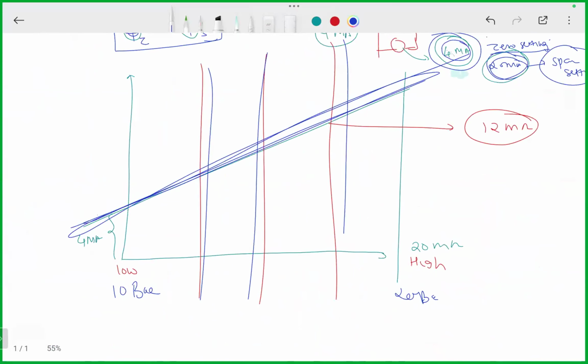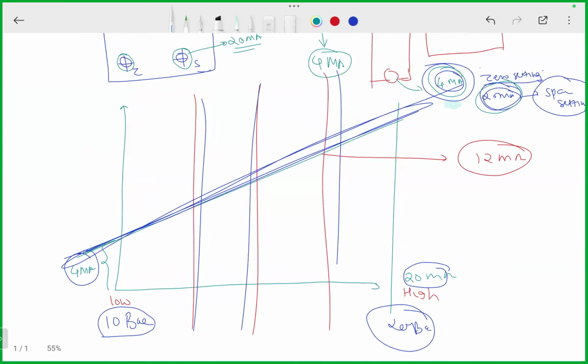Whatever is the maximum value you are trying to measure, corresponding to that you adjust your DP transmitter to generate an output of 20 milliamp. Whatever is the lowest value - pressure, flow, temperature, anything - you adjust your controller to generate a 4 milliamp signal. So I can always draw this line. Can we draw this line?